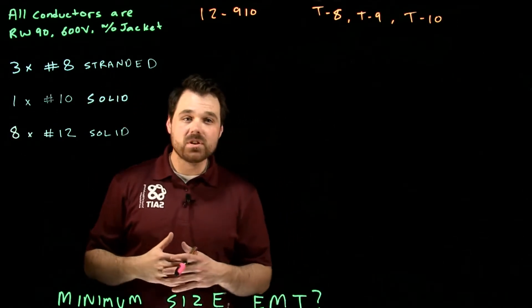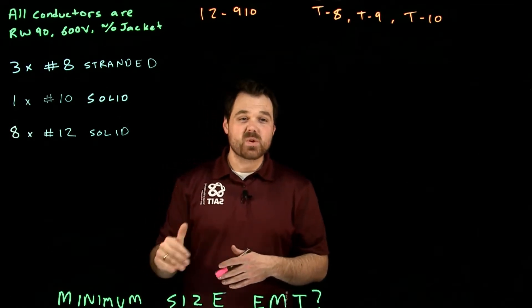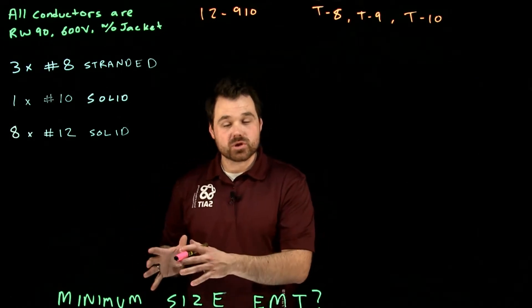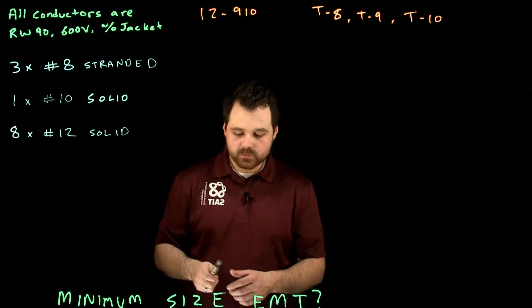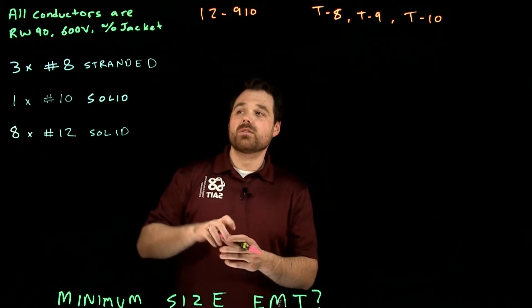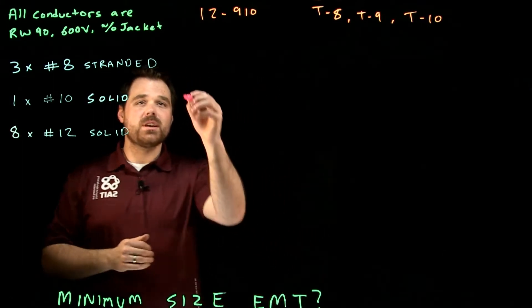And this is something you'll see quite often in the field as we only have sizes 14, 12, and 10 that come in solid. Everything above that is stranded. So in this application, for our number 8s, we're actually going to go to table 10-A.